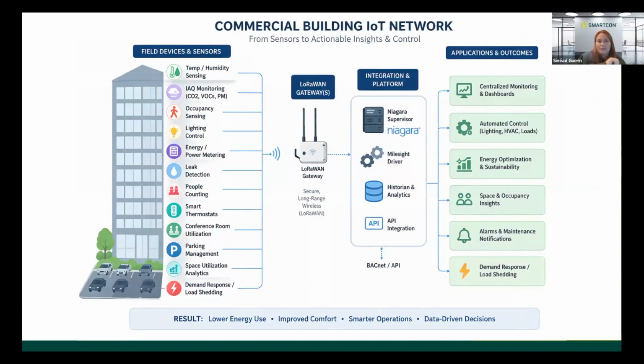Temp and humidity sensing, IAQ monitoring, occupancy sensing, lighting control, energy, leak detection, people counting - we're pulling in all of this information to work together. We'll notice if a person is in the space and control the lighting, control the HVAC. For IAQ monitoring, you can do demand control ventilation by measuring the amount of CO2 in an area. You don't have to always run the exhaust at 100%. You can control the damper to let out a certain amount of air depending on how many people are in there. If 100 people are in a room, it's a bigger concern than if only 5 are in there.